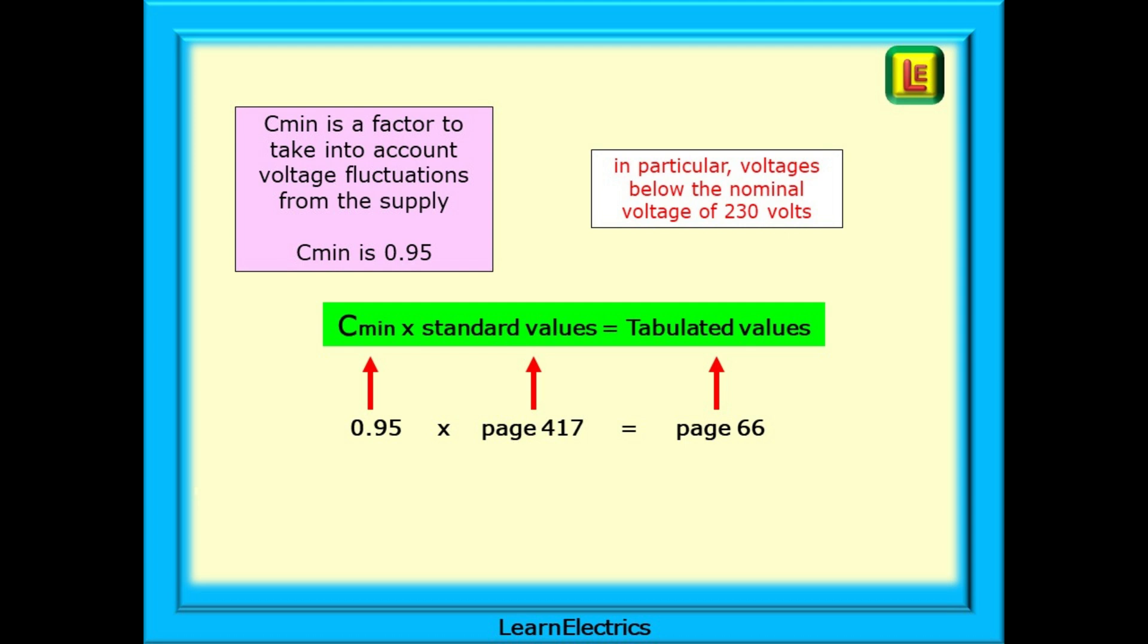That the voltage minimum might only be 95% of the nominal. We're interested in fluctuations below 230 volts because if the voltage reduces then the fault current will also reduce and we may not get our required 160 amps. If we multiply the standard values from page 417 by Cmin we will get the tabulated values as shown on this page.